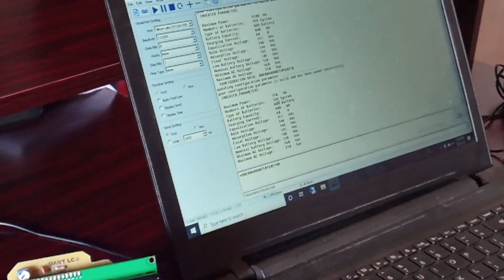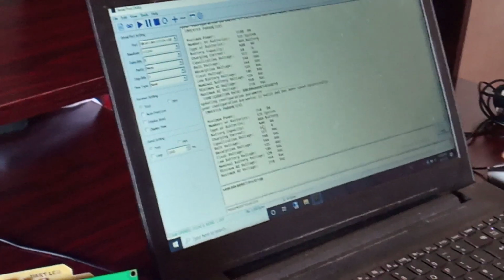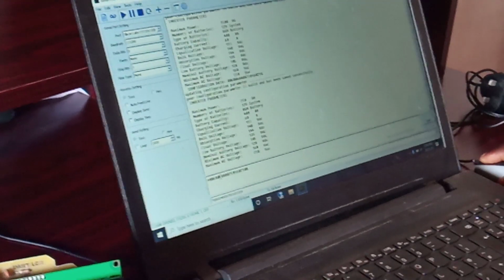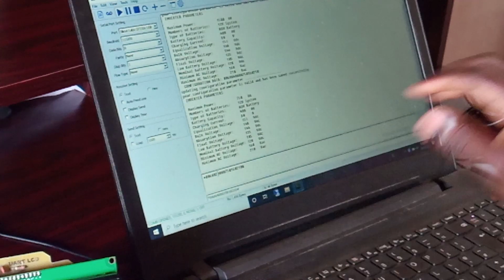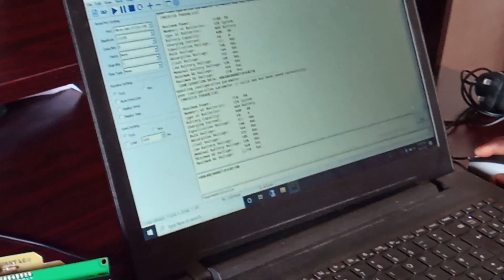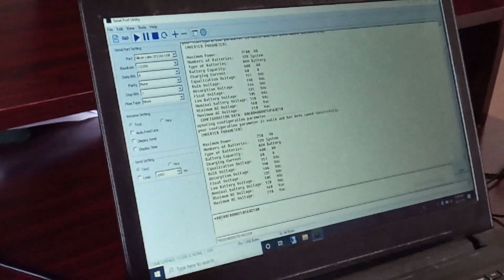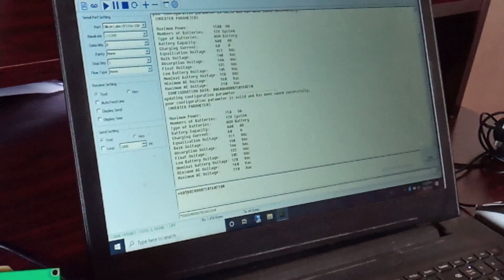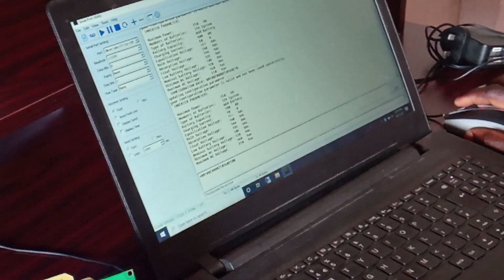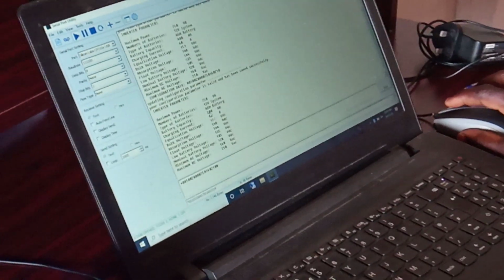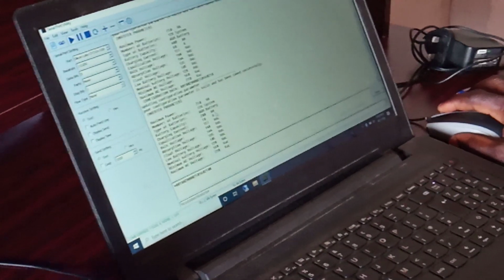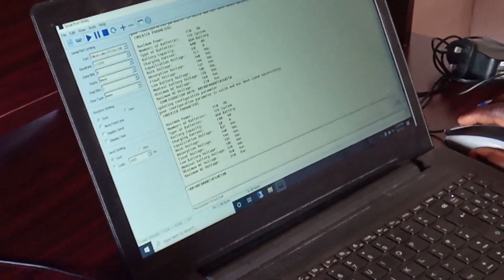Let's say we are going to be doing a 200 amp hour battery. We'll go to our parameter setup and change that 4 to 2. Let's say we are changing the charging current to 10 amps. You can change the 6 to 1. Let's send and see. Okay, we've seen that the battery capacity has actually changed to 200 amp hour. The charging current has changed to 10 amps.